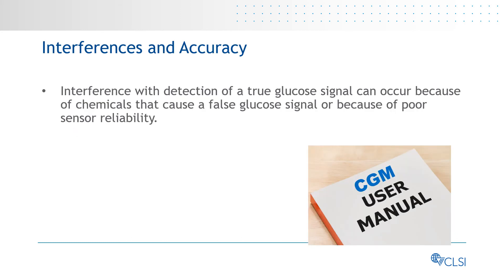Interference with detection of a true glucose signal can occur because of chemicals that cause a false glucose signal or because of poor sensor reliability. Therefore, testing should be performed for sensor-specific physiologically occurring substances, exogenous substances and drugs, as well as for poor sensor reliability, all of which can affect the accuracy of these devices. It's important to recognize the presence of these factors when assessing the accuracy of a CGM system.